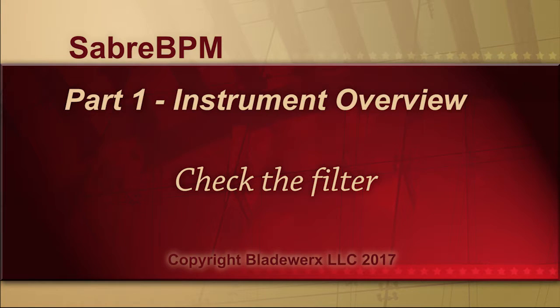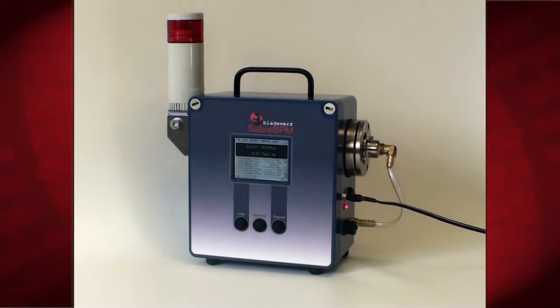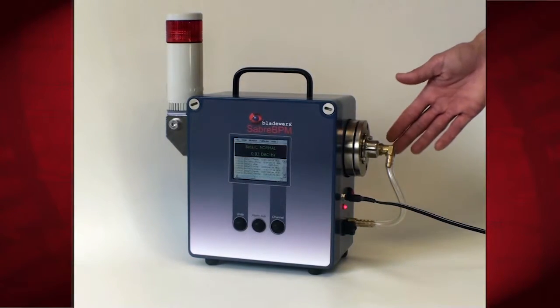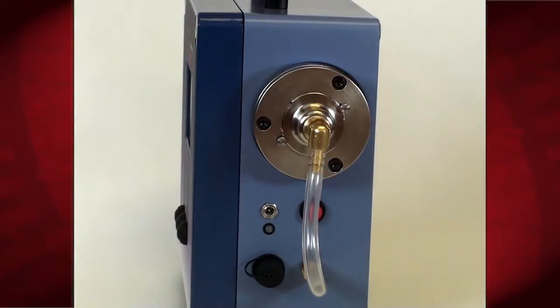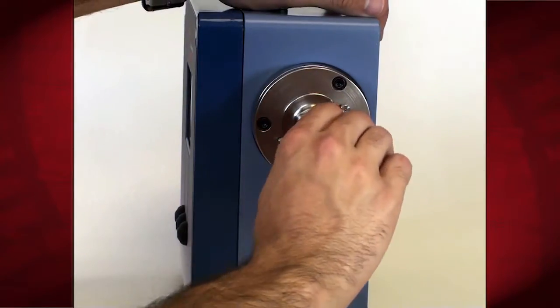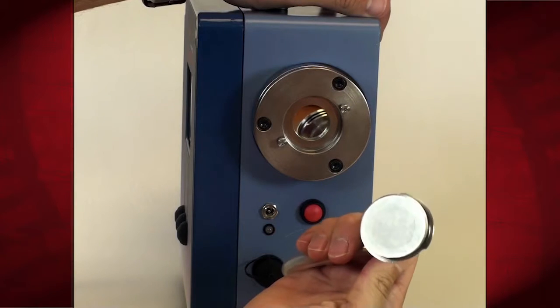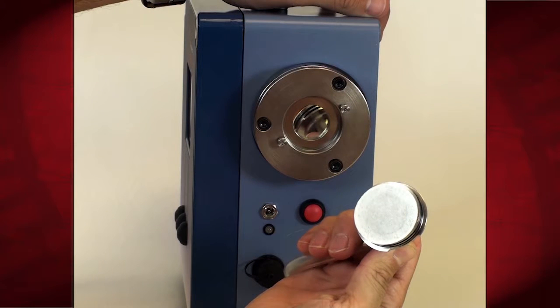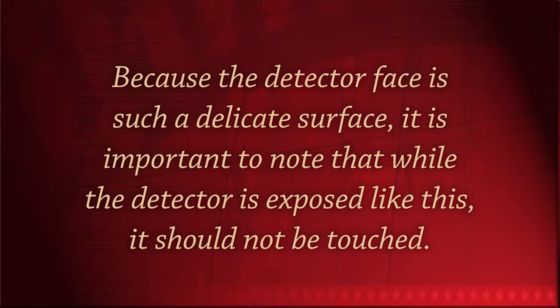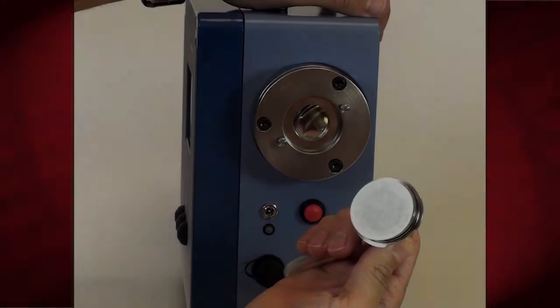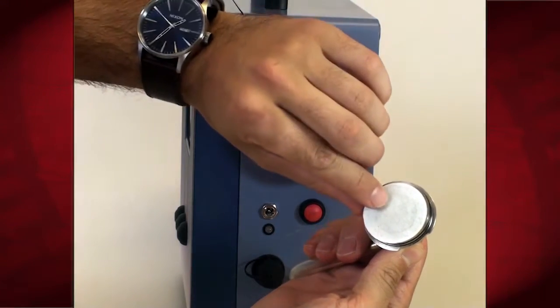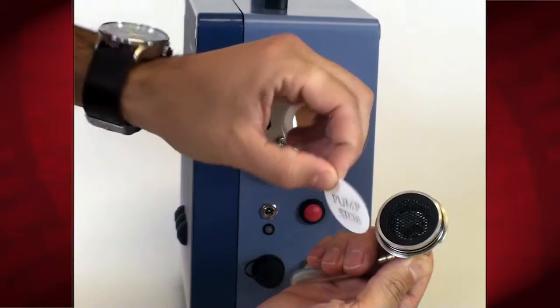Now let's take a look at the filter to make sure one is installed correctly. On the radial entry sampling head, the silver component protruding from the right side, just twist the filter holder until the notches on the cap line up with the screws and pull it out. You should see a white filter being held against the filter holder by the pump suction. Because the detector face is such a delicate surface, it is important to note that while the detector is exposed like this, it should not be touched. Peel the filter off from the edge, being careful to not damage the face of the filter.